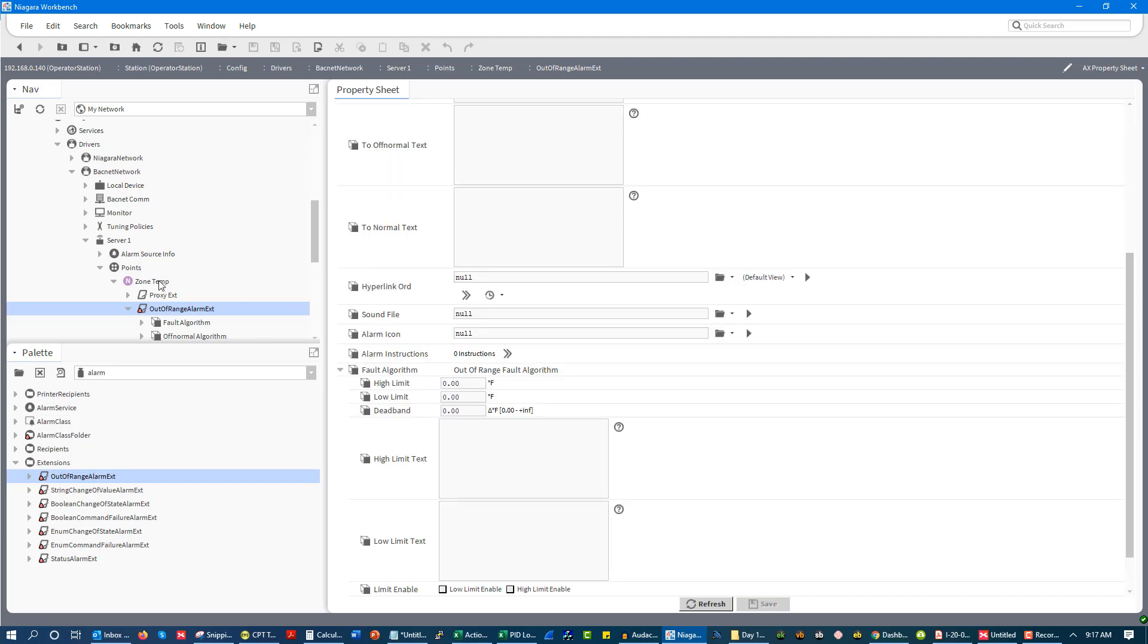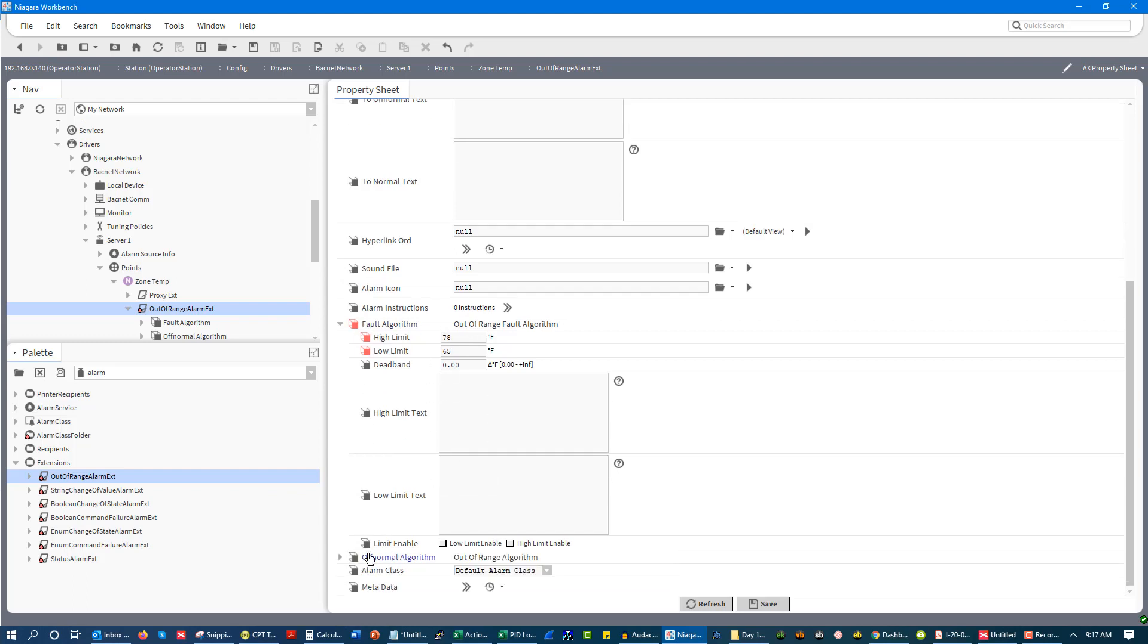I could say this is zone temp and I'm going to set up a high of 78 and I'm going to set up a low of 65. And if I want to, I could have a dead band. I'm not going to put that in there. I'm just going to say if it goes above 78 or if it goes below 65, I get my fault, my alarm.